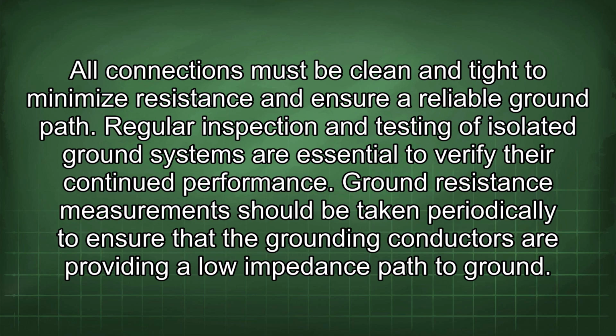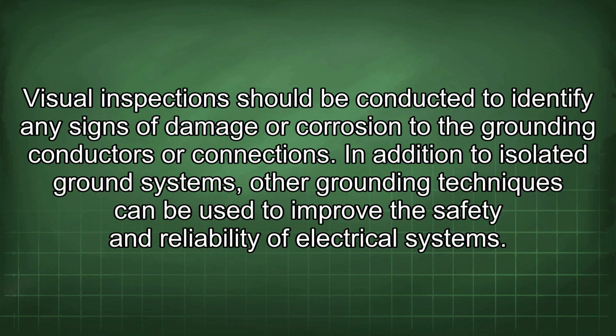Regular inspection and testing of isolated ground systems are essential to verify their continued performance. Ground resistance measurements should be taken periodically to ensure that the grounding conductors are providing a low impedance path to ground. Visual inspection should be conducted to identify any signs of damage or corrosion to the grounding conductors or connections.